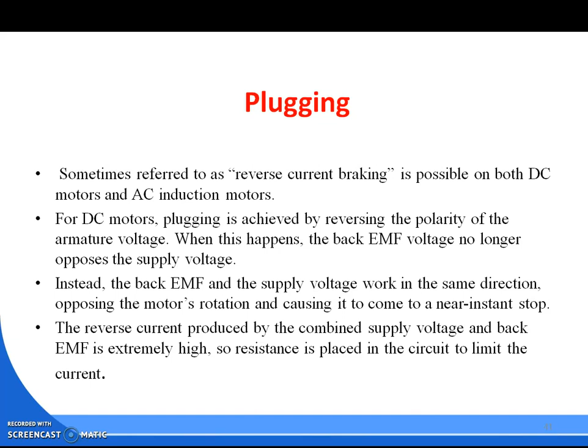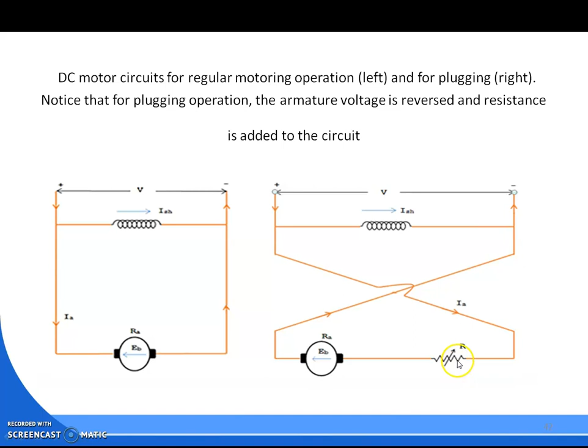In this type of braking, both the supply voltage and the back EMF work in the same direction, opposing the motor rotation and causing it to come to a near instant stop. The reverse current produced by the combination of supply voltage and back EMF is extremely high, so resistance is placed in the circuit to limit the current, as shown here.